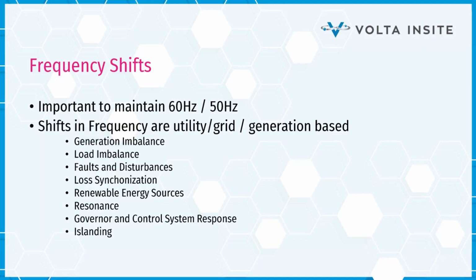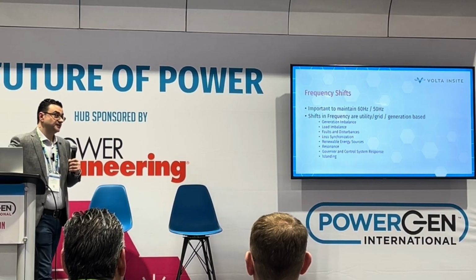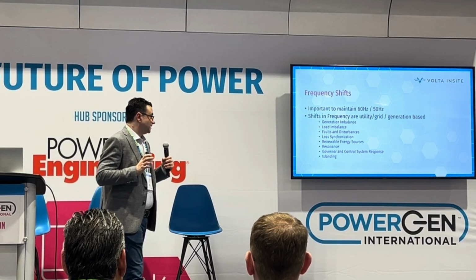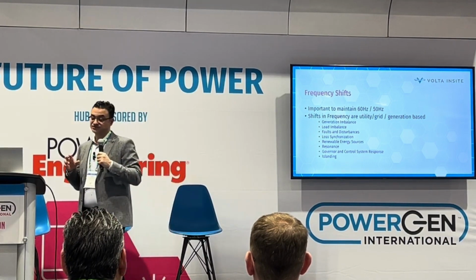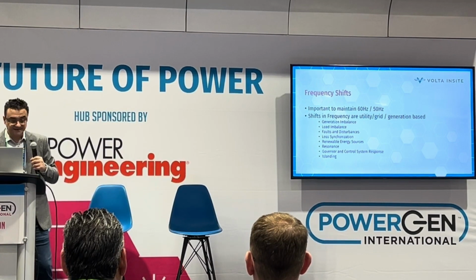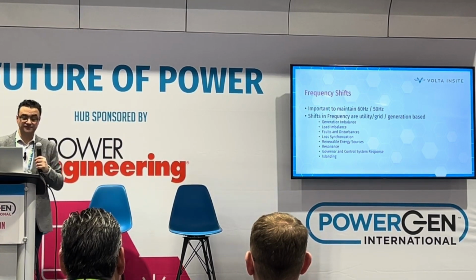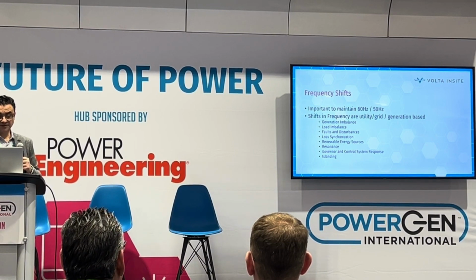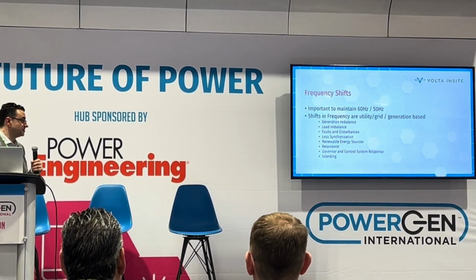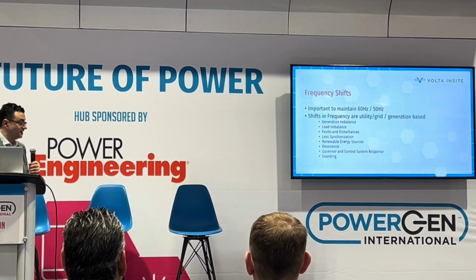And then we have renewable energy sources, which are injecting a lot of harmonics into the utility, which can also drag down the governor circuits of your generators. And there's resonance as well as islanding. If you take a section of the grid off, the remaining generators within that island may not be able to carry the full load. The only way to get around this, if you're experiencing a lot of it within a facility, is to go down the path of a UPS.